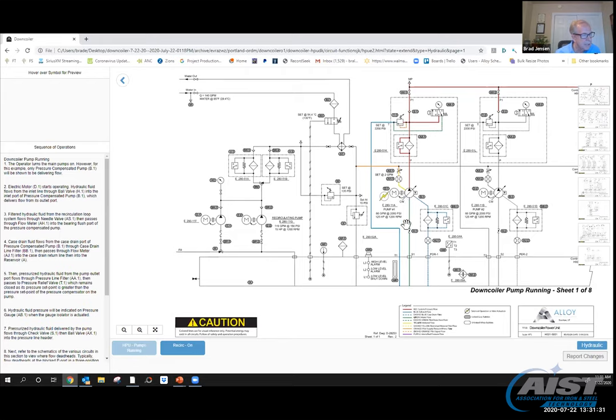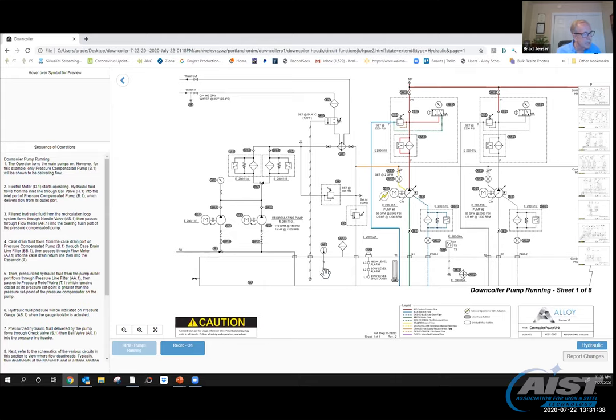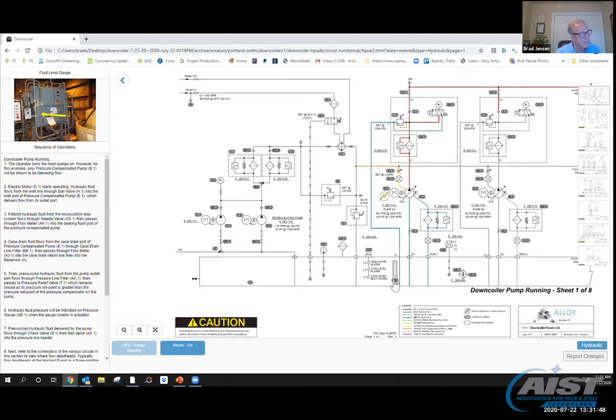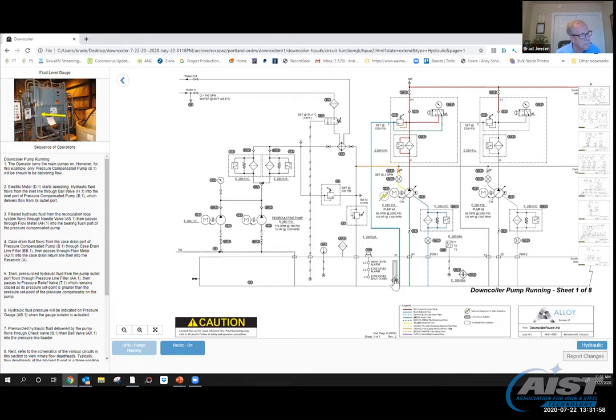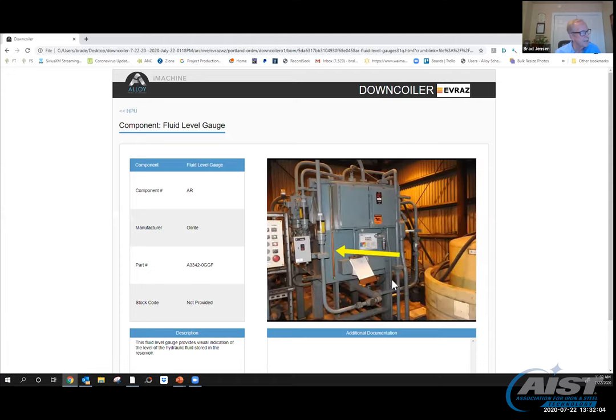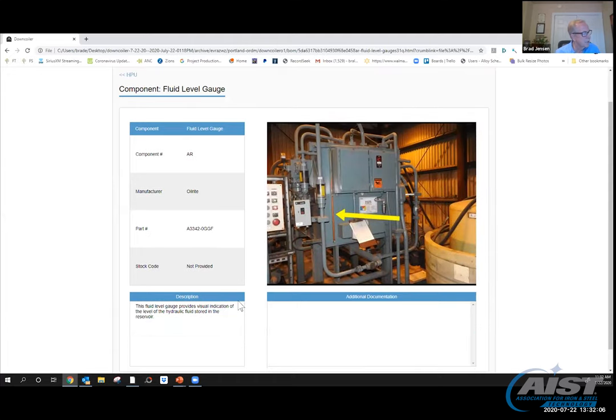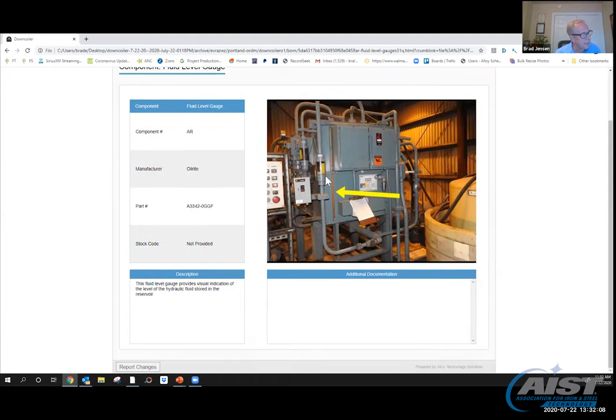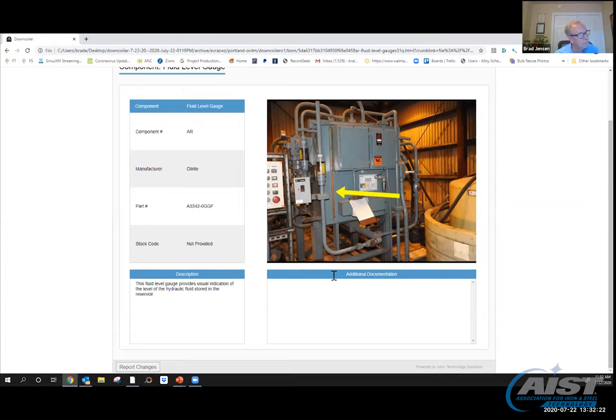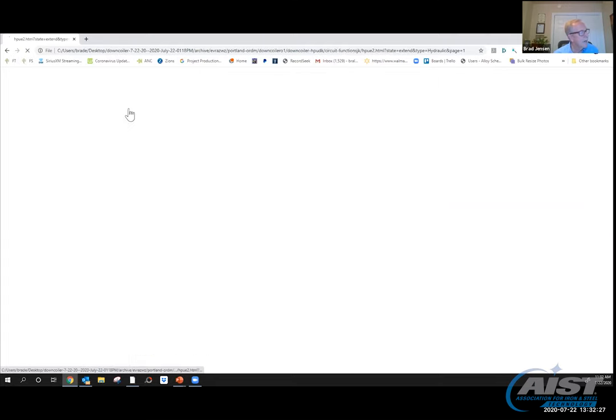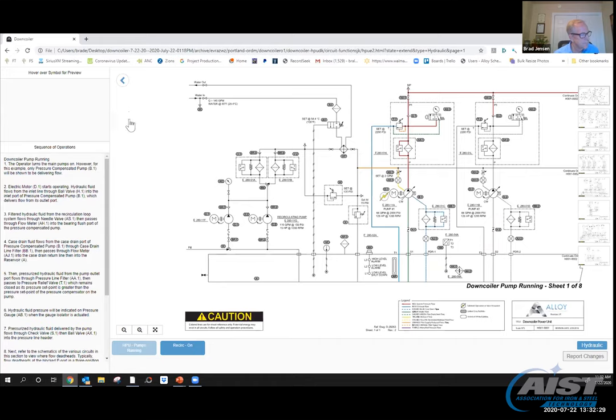Once they are combining with this main header up here, our main pressure line, they're running down to these various valve stands and each valve stand has its circuits on it. The minute those pumps are fired up, flow is going all the way down to the P line of all these valve stands ready for those valves to be energized to make work happen. For now I'm going back up to my pump that I've designated or colored 'running pumps running.' By the way, they would all be the same configuration except perhaps the one on standby. You'll notice I've got the reservoir down here and the reservoir is where the pump is drawing its fluid from. This is the inlet to the pump.